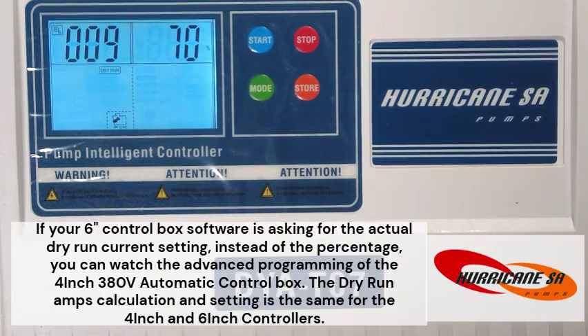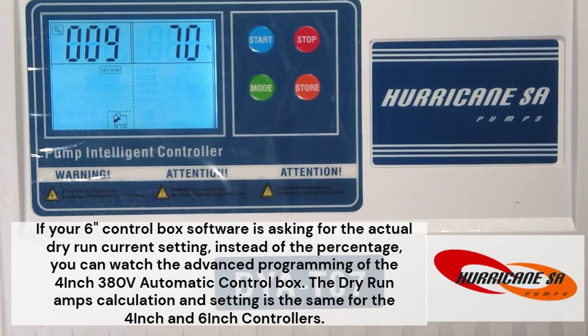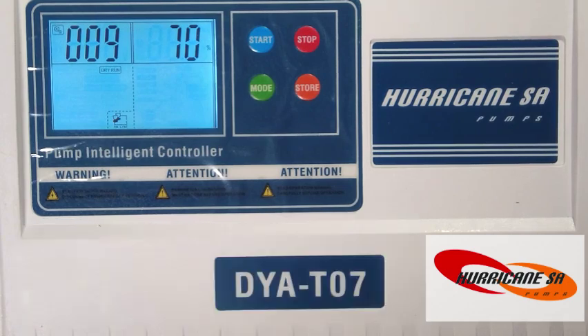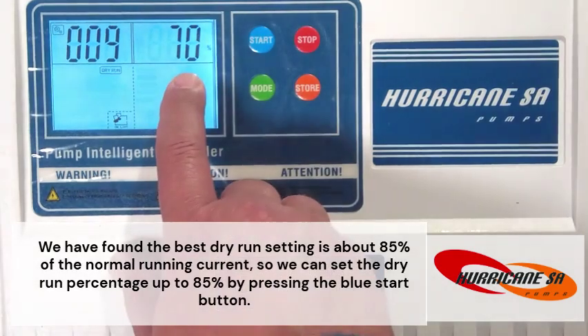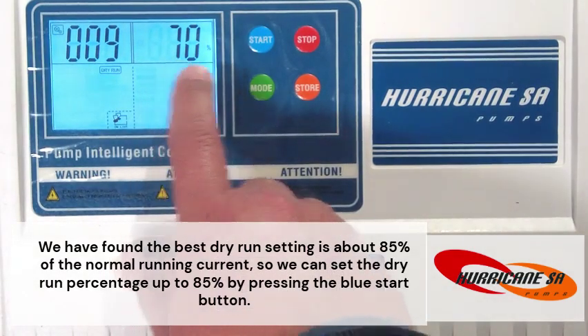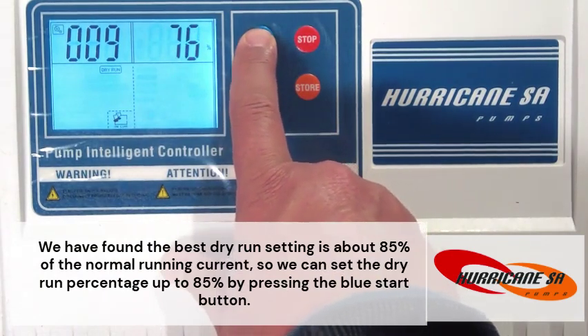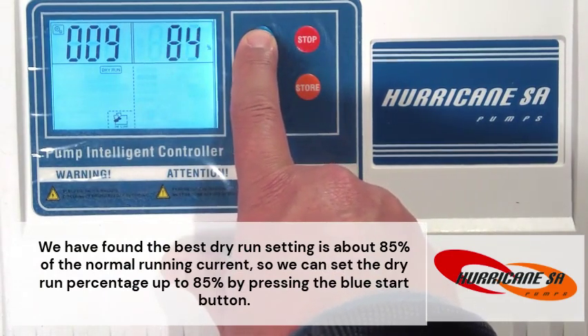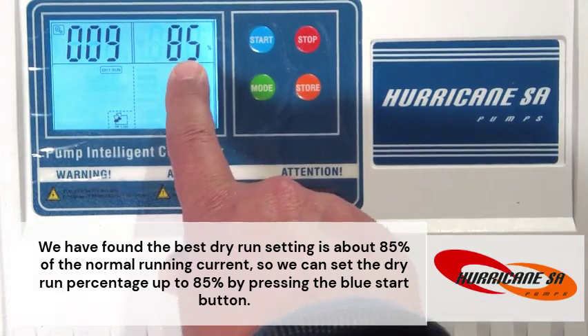If your 6-inch control box software is asking for the actual dry run current setting, instead of percentage, you can watch the advanced programming of the 4-inch 380V automatic control box. The dry run amps calculation and setting is the same for the 4-inch and 6-inch controllers. We have found the best dry run setting is about 85% of the normal running current. So we can set the dry run percentage up to 85% by pressing the blue start button.